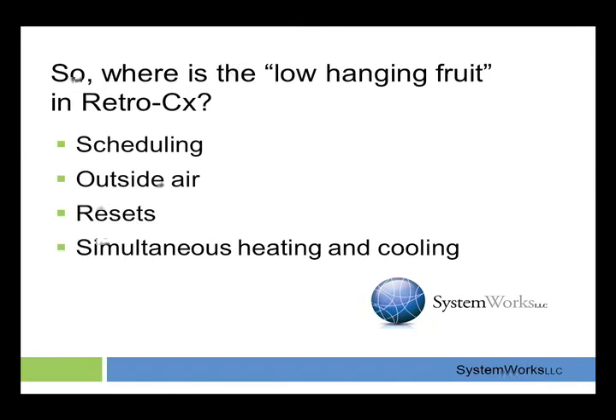And I know this is going to make people kind of smirk, but we find units running 24/7 and they leave the outside air on at night, bringing in large quantities of outside air and heating and cooling it when there's nobody in the building. Obviously, if the unit is going to run in the evening, it should have no outside air and run on 100% return air, so you're not conditioning outside air unnecessarily.